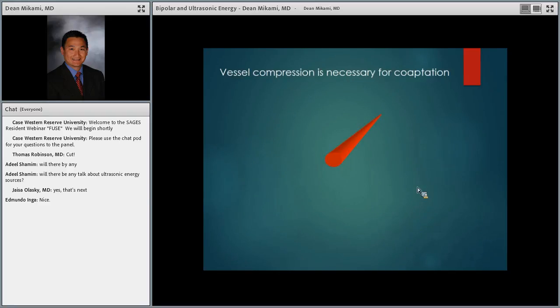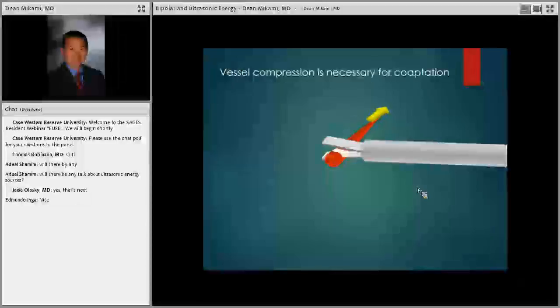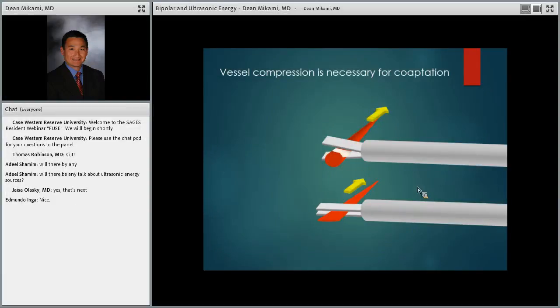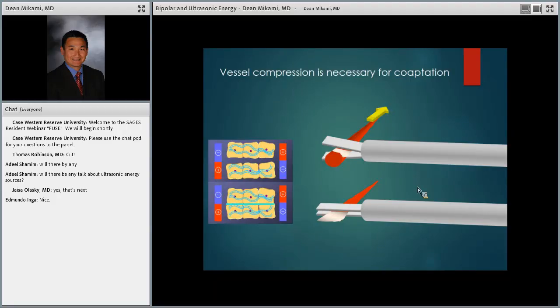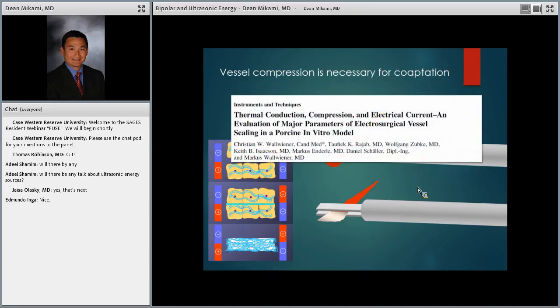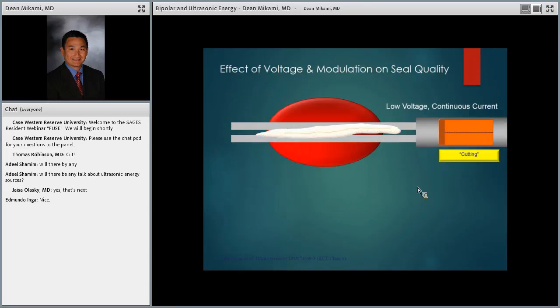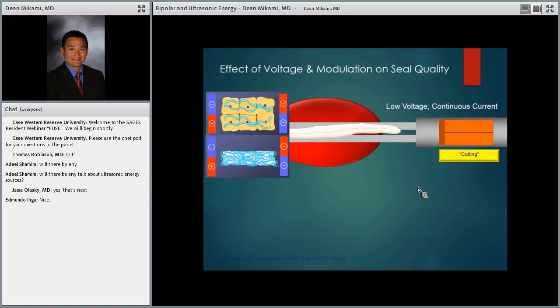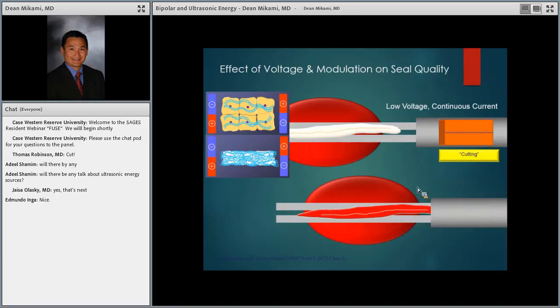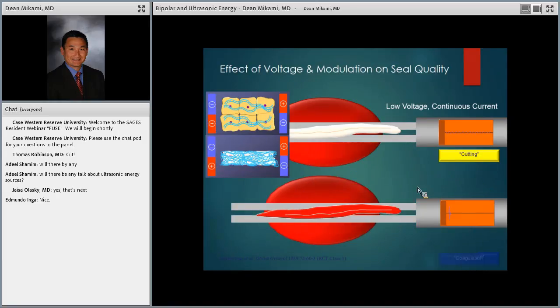So what do you need for bipolar devices? You need coaptation. Coaptation means we're going to actually depress the tissue, and the more coaptation we get, the better the tissue seal is. And we saw this before here. So you really want to coapt the tissue so you get a very good seal there. So once again, in the bipolar mode, we're using a cutting waveform. We have low voltage continuous current there. So most of the new advanced bipolar instruments and systems use a low voltage, not continuous, but they use an intermittent current, and I'll discuss this in the next slide here.